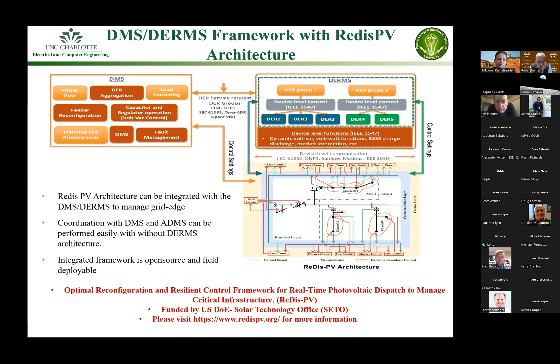The field architecture looks like this, where you can see the historical data log coming from the utility. This can be through archival, maybe a PI server or other server archival at the utility level. We deployed this on a 1 megawatt PV station with a battery energy storage of 250 kW, 750 kWh, with inverter capacity of 1 MVA on a radial distribution system. Using the historical log, we look at 3 functions: renewable energy capacity firming, renewable time shift, and voltage support.